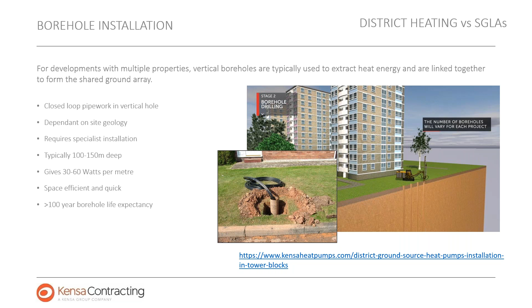I'd like to quickly just talk you through a project that was completed in October 2018. The heating side of that project was completed by ourselves in 2018. This is for Enfield Council. The principal contractor on that project was Engie. It is still England's largest shared loop district ground source heat pump installation. Over 8 tower blocks supplying up to 402 individual flats. There is an expectation, and that has been realised, of a 50% savings on residents' heating bills. There's significant CO2 emissions reductions across those 8 blocks.